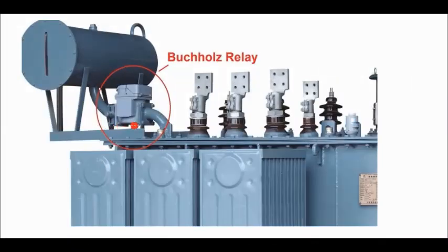Normally, the Buchholz relay is mounted in between the pipeline which connects the main tank of the transformer and the conservator tank. So this is the Buchholz relay. So what is the purpose of the Buchholz relay? The Buchholz relay mainly detects three types of fault.